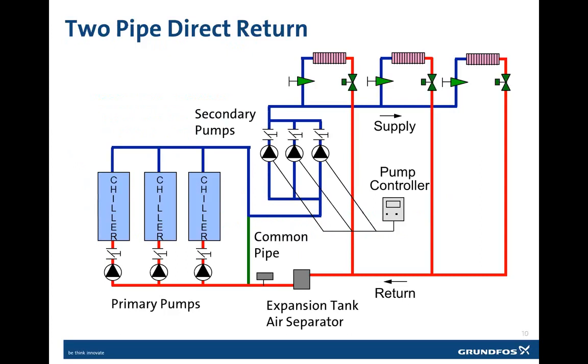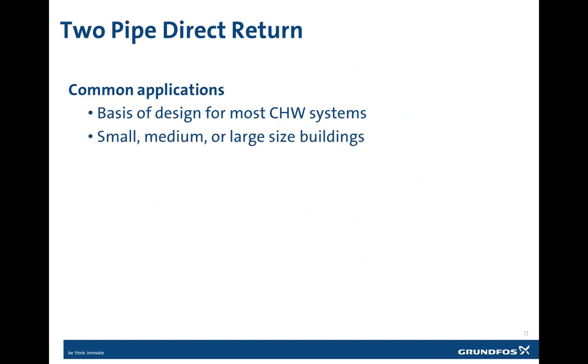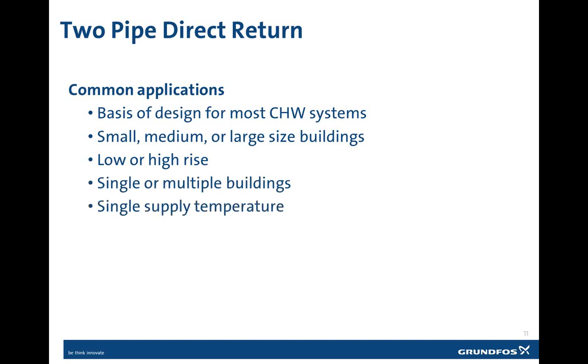We can see listed here, on the left side of the system, our primary pumps. Then we have our secondary pumps. On the bottom we have our main common pipe with our expansion tank as well as our air separator on the return. And these pumps are controlled by a multiple pump controller. Now, some of the applications for the two-pipe direct return: it's the basis for most chilled and hot water systems, and it can be found in larger, smaller, as well as medium-sized buildings, from low to high-rise systems, single or multiple buildings. And there's also less operational flexibility, since each building sees the same supply temperature to the application as well.